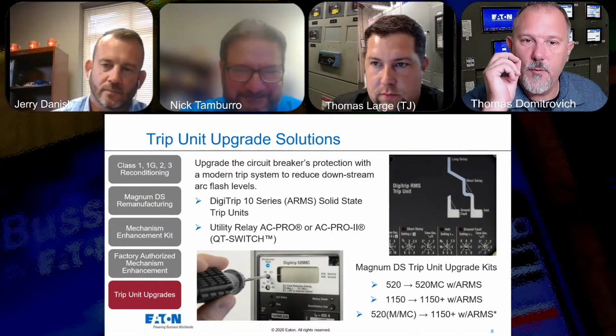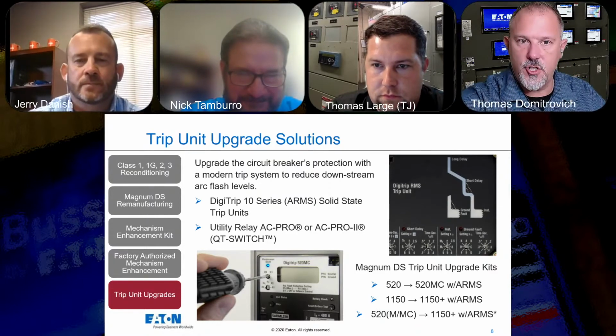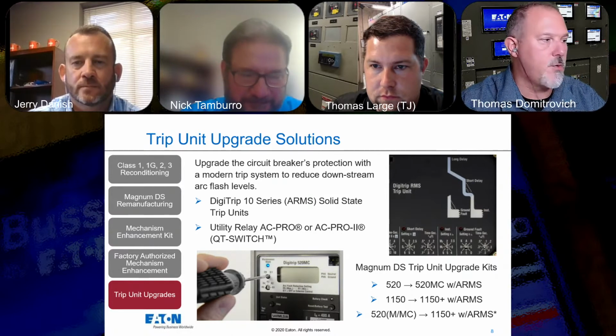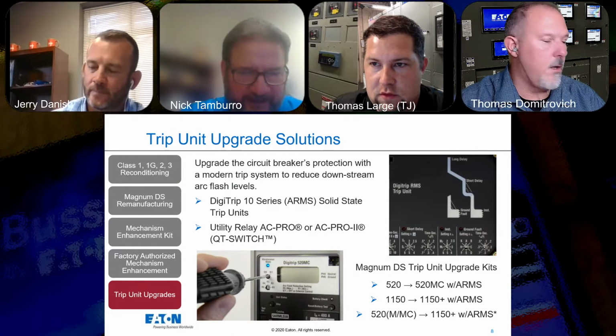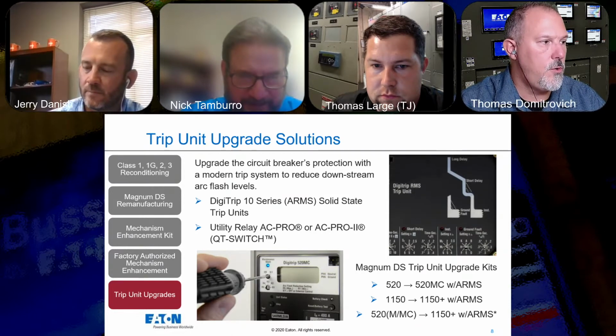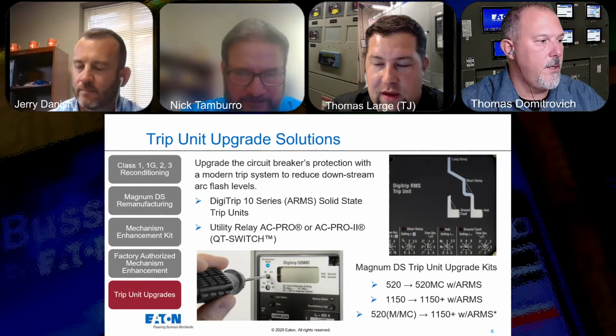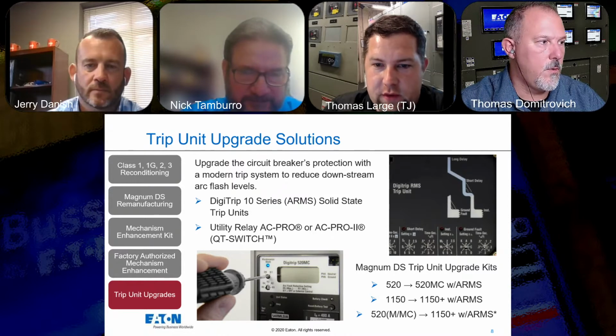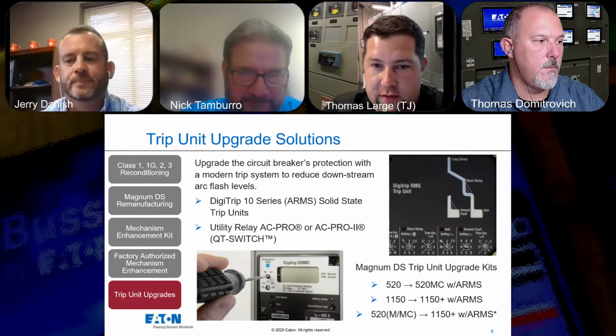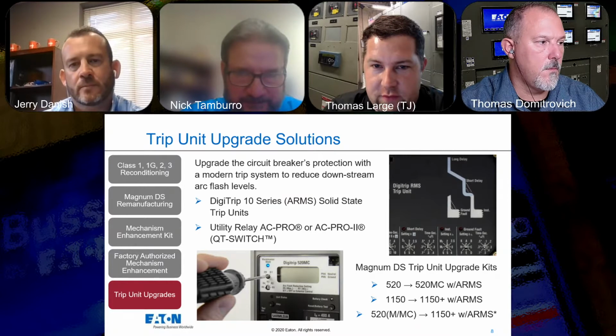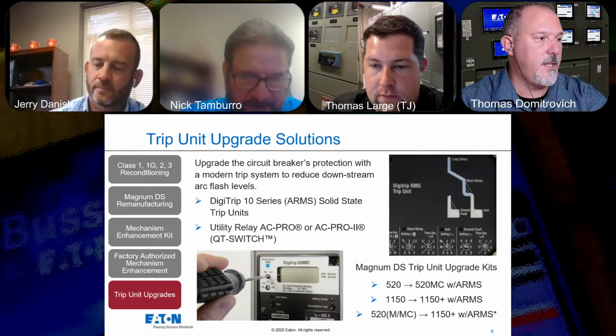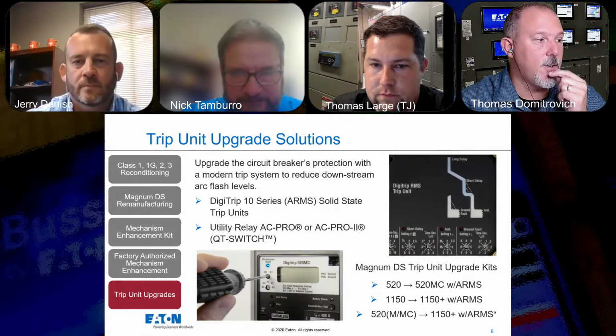So you're saying, Nick, that we have packages to say this trip unit can be put on these models of GE breakers or Square D breakers or whatnot. Right. Yeah. And I could say between utility relay, AC Pro, and Eaton, you're probably covered. Okay. I've yet to encounter a model that we can't provide this for. And one thing to talk about is that when we add these features, the arms and quick trip, we functionally test those features before they go out the door. So we do verify the faster clearing time when we're doing the testing. Oh, really? Okay. Cool. And yeah, because you have all the test units up there, so it's not as hard to do once you're in that facility. I'm just feverishly looking for the listing.